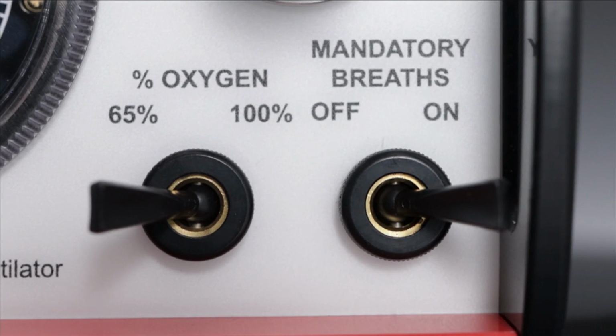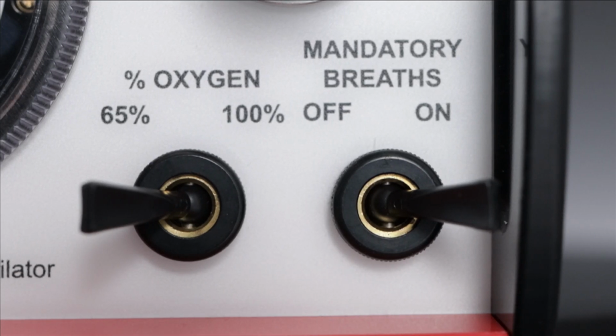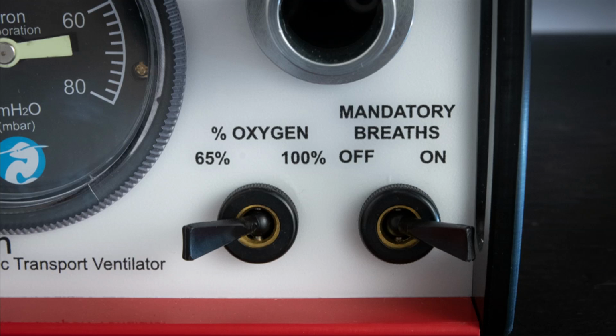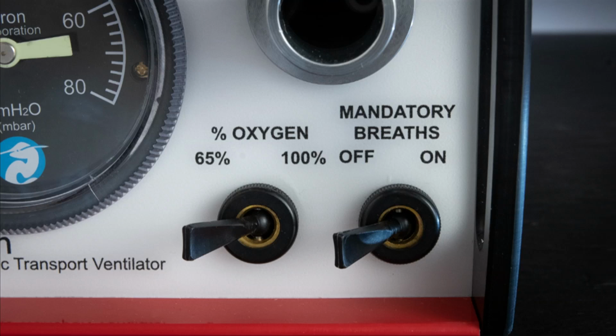Mandatory breaths. The mandatory breath control to the far right allows you to toggle on or off. In the on position, the ventilator will deliver the preset tidal volume and respiratory rate for each mandatory breath for the patient. With the mandatory breath switch in the off position, the ventilator will provide CPAP only for the spontaneously breathing patient via an endotracheal tube or face mask.